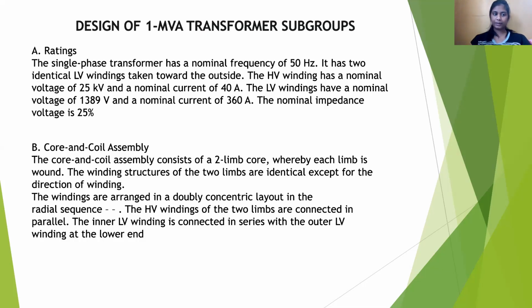Core and coil assembly. The core and coil assembly consists of a two-limb core, whereby each limb is wound. The winding structures of the two limbs are identical except for the direction of winding. The windings are arranged in a double concentric layout in the radial sequence. The HV windings of the two limbs are connected in parallel. The inner LV winding is connected in series with the outer LV winding at the lower end.